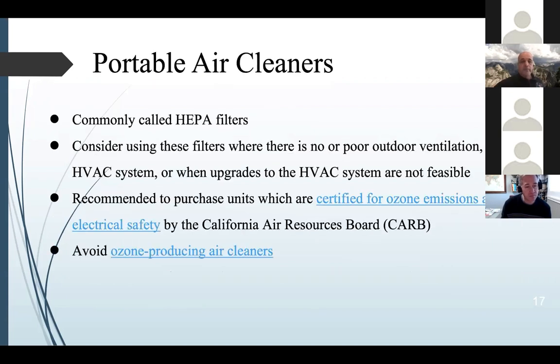Back to portable air cleaners. The best ones are commonly called HEPA filters. I do have some concerns with them though - they're not a substitute for good ventilation. They do work and are effective at removing much smaller particles and viruses, but they can be expensive. If you're on a limited budget and want to improve building performance, good ventilation is, in my opinion, more helpful than a portable HEPA filter, especially if they're not sized correctly.